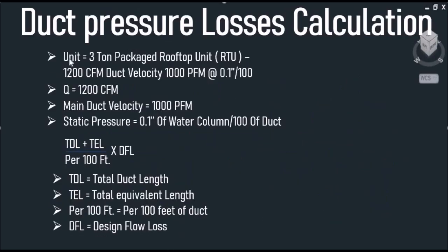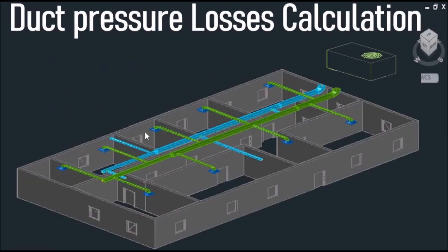For this example we are going to be using a 3-ton package rooftop unit, which is equivalent to 1200 CFM with a velocity of 1000 FPM for our main duct at a static pressure of 0.1 inch of water column. To calculate the pressure losses we will use the formula: (TDL + TEL) / 100 × DFL, where TDL is total duct length, TEL is total equivalent length, 100 is per 100 feet of ductwork, and DFL is design flow loss.